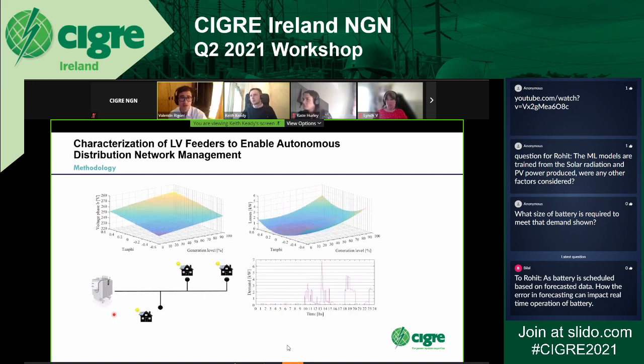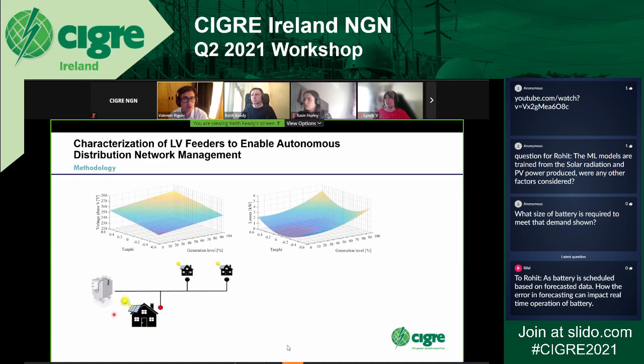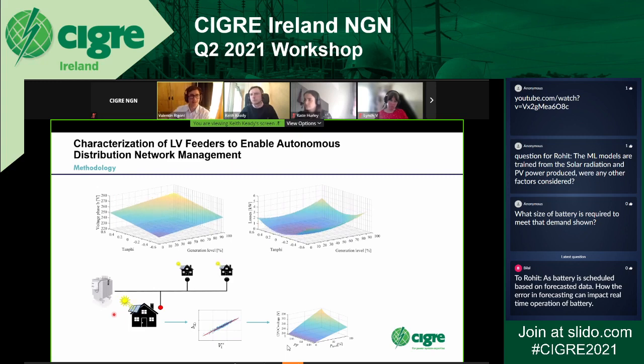And then we started exploring as well how these surfaces would be affected by changes on the demand on the system, changes on the voltage at the distribution transformer level because of the operation of the medium voltage grid, etc. And we found that there was a way of correlating all these surfaces to local measurements at every point of the grid. So basically, we created a method where if you have access at a PV location to the local voltage and the local power injection from your PV inverter, you can use the regression model in order to obtain a surface that characterizes how the network is in its current state.